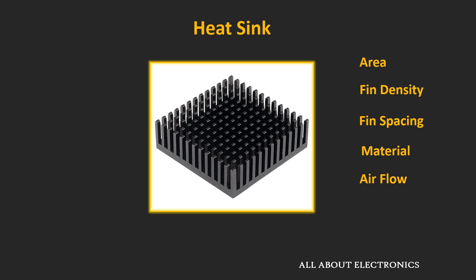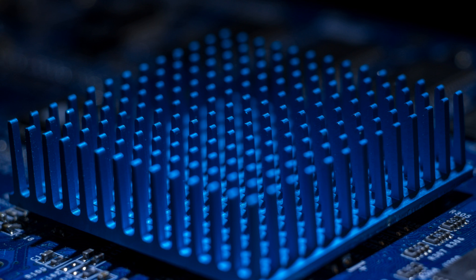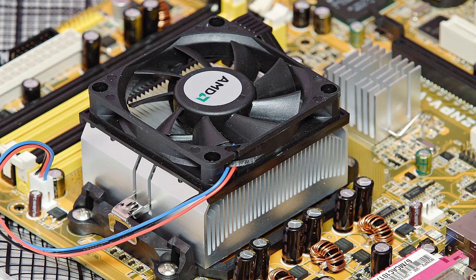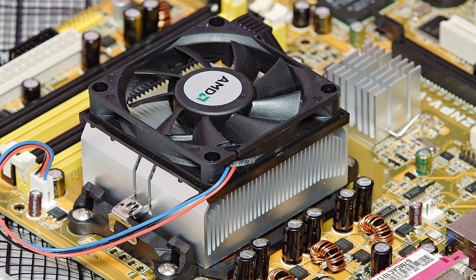The performance also depends on airflow. Speaking of airflow, heat sinks can be classified into two categories: active heat sinks and passive heat sinks. In a passive heat sink, there are no mechanical moving parts and heat is transferred through natural convection. In an active heat sink, heat is transferred using forced convection, and a device such as a fan or blower is used. Due to forced convection, active heat sinks can remove heat more efficiently and require less space for the same heat transfer, but they require more maintenance because of the mechanical moving parts.